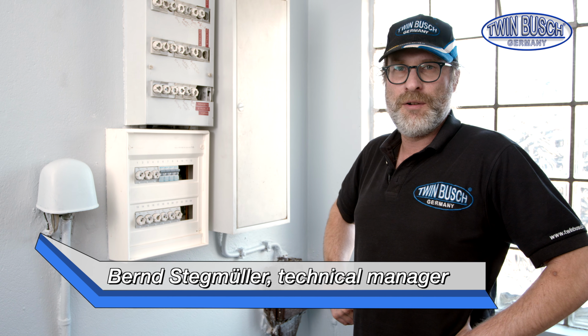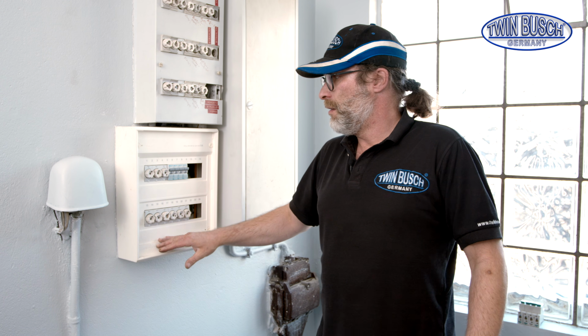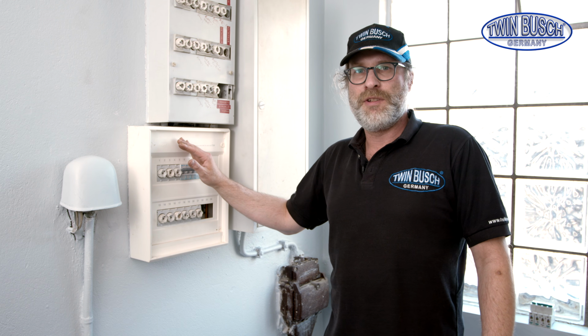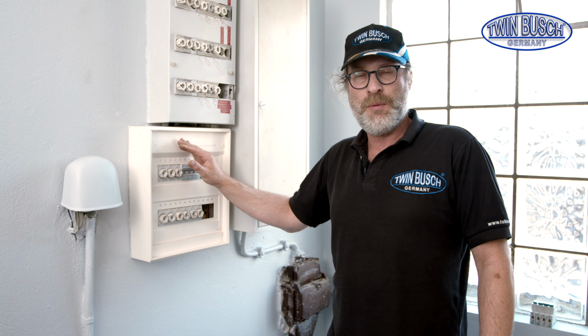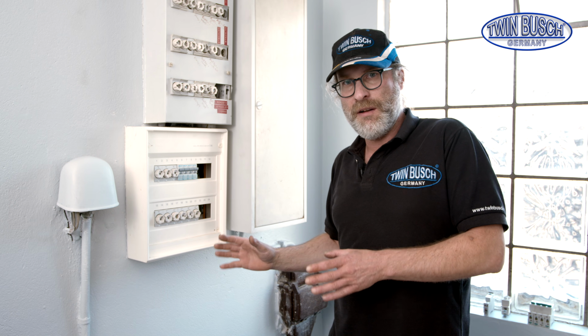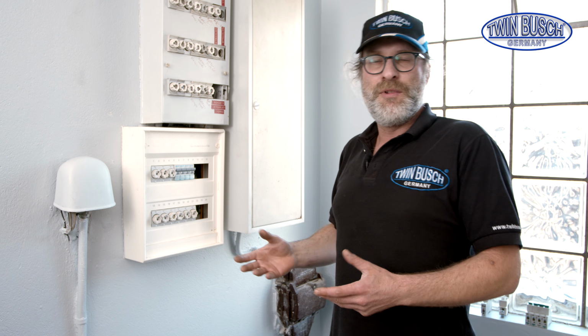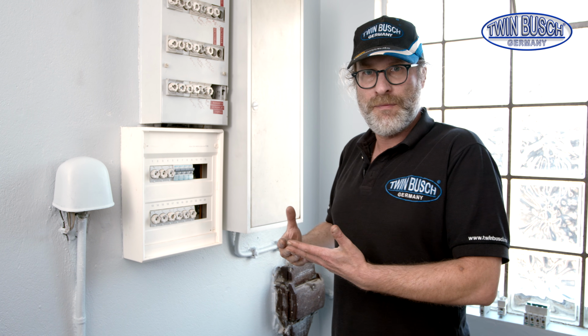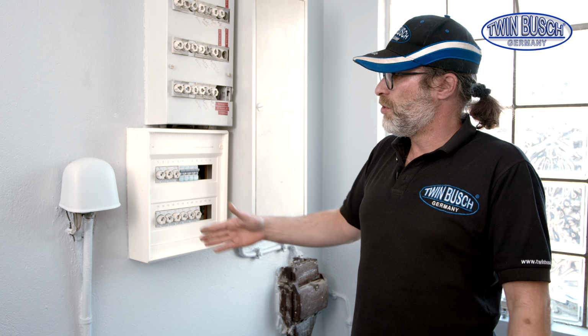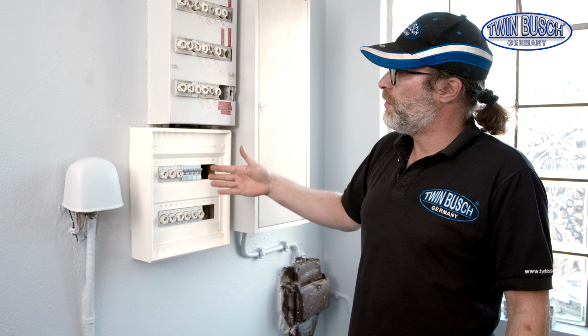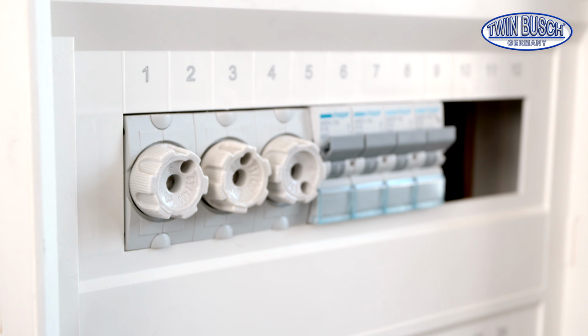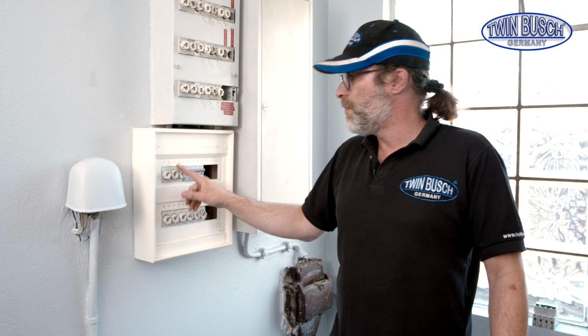This video focuses specifically on the electrical connection of a lift. In this case, basics of the supply up to the lift. Especially for lift models with a 2.2 kilowatt 230 volt drive motor, there is a relatively high starting current when the motor starts up. And it must be protected accordingly in the sub-distribution or in the fuse box. There are a few indications to consider.